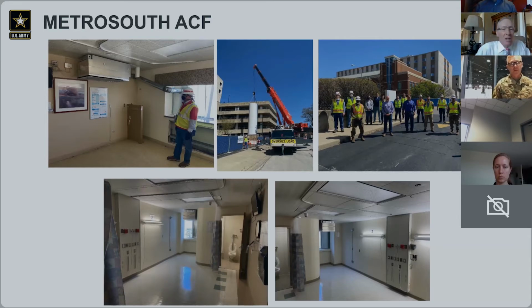So two things happening there. Number one, we could recycle the air internal to that room through a HEPA system, but we'd be unable to create the negative pressure necessary given the bones of that building. So we're really killing two birds with one stone. That system allows us to filter the air up to 12 times per hour and then create a negative pressure system in that room, pulling the air out, cleaning it, and spitting it out of the building.